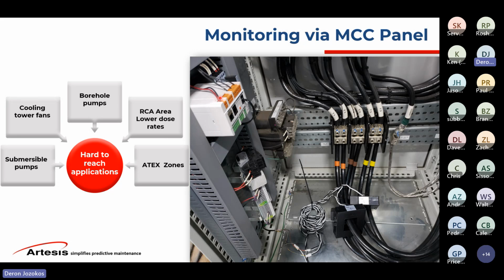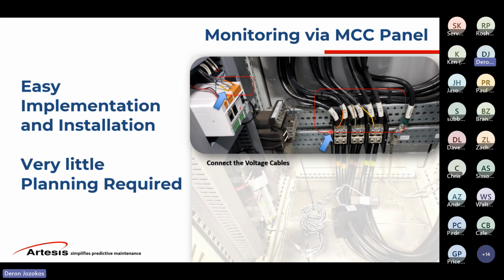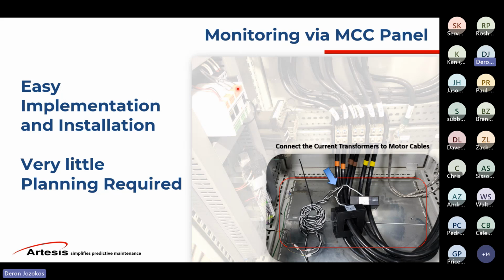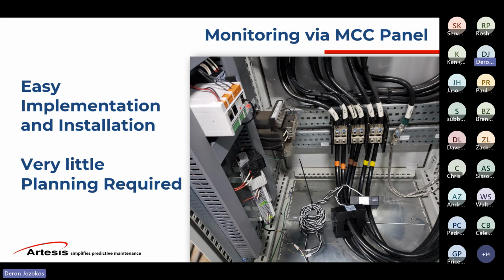Okay, so here we have the power supply supplied to the EMCM, a 120 volt power supply. Now let's grab the voltage from each phase. Very simply, 12 or 14 gauge wire, right from, say, this terminal block here, and terminate that into the EMCM phase 1, 2, 3. Now, you told us the full load amps of the motor. We supply you with the correct sized CTs, which are customized for us. They're clamp on. You just simply open them up, clamp on, plug it into these little clips here at the bottom, and then plug that RJ45 connection into the EMCM, a telephone jack basically. So we supply this cable, 3 little clips at the bottom, clamp on, clip in. So maybe this took us 15 minutes.